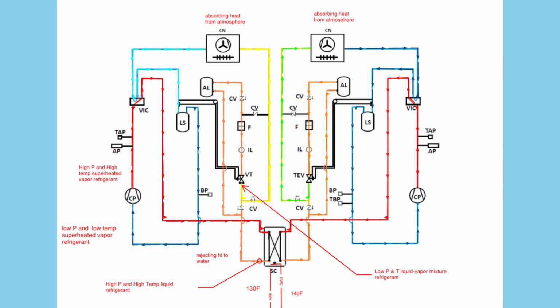4. Expansion. The refrigerant passes through the expansion valve, where it undergoes throttling. Its pressure and temperature drop sharply. The refrigerant leaves as a low-pressure, low-temperature liquid vapor mixture. 5. Heat absorption, evaporator, outdoor coil. This cold refrigerant mixture enters the outdoor coil, which now acts as the evaporator. Even in cold weather, the outdoor air contains usable heat. The refrigerant absorbs this heat from the ambient air, boiling into a vapor. The air leaving the coil is cooler, and the refrigerant is now a low-pressure vapor.